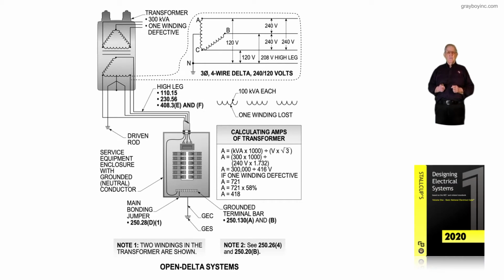Now this illustration deals with open delta systems. Now figure 4-6 illustrates such a system. Now let's review the windings in the above portion of the illustration. Now notice we only have 2 transformer windings. We've either lost one or we've gone completely open delta.